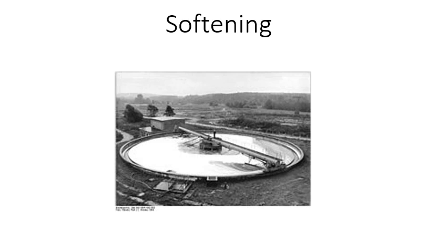Caustic soda can be used to remove hardness from water. When reacting with CO2 and carbonate hardness, caustic soda forms sodium carbonate, permanent hardness. Why use lime instead of caustic soda? Lime is much cheaper. Using 50% caustic soda has some advantages. It's more stable for storage, there's less sludge byproduct, and it is easier to store and handle than lime.